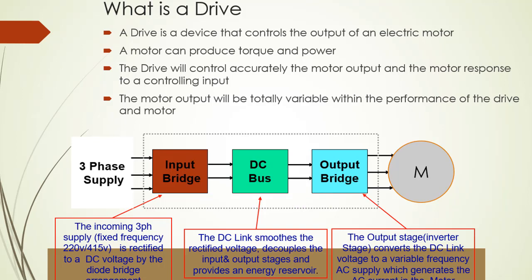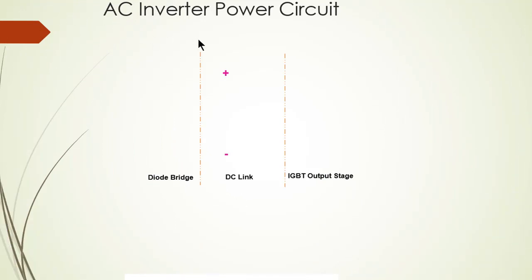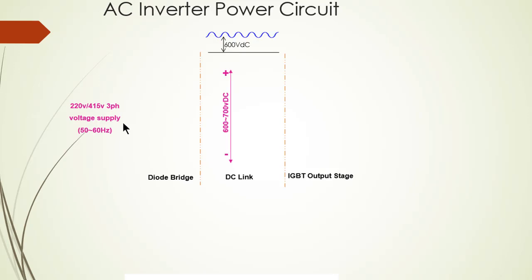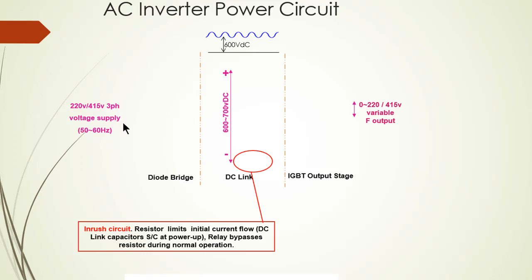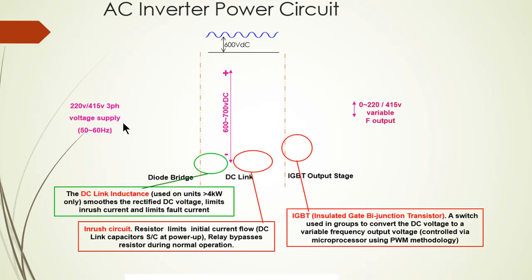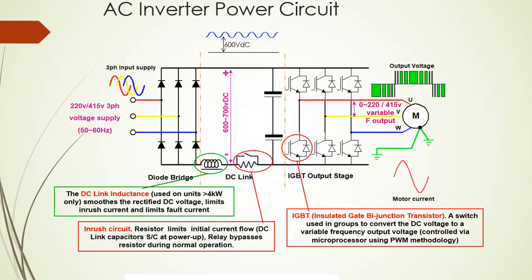The DC link smooths the rectified voltage, decouples the input and output stages, and provides an energy reservoir. The output bridge section then converts the pure DC from the DC bus — that is, the DC voltage — to AC voltage. The output bridge, or inverter stage, converts the DC link voltage to a variable frequency AC supply.